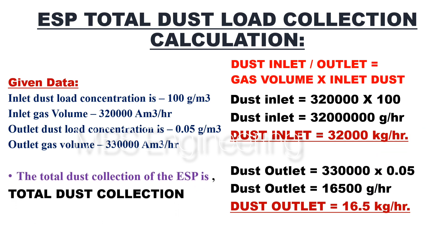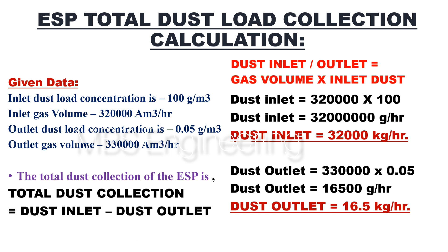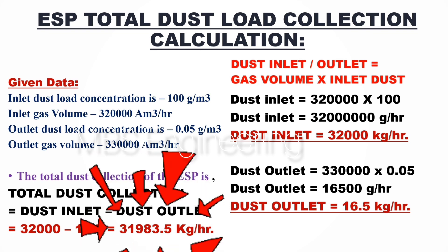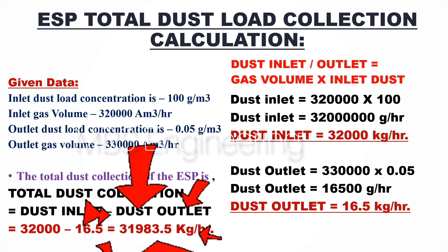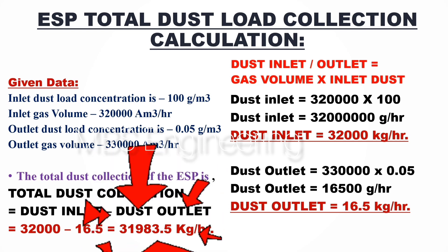Finally, total dust collection is equal to the dust concentration at inlet minus dust concentration at outlet — that is, 32,000 minus 16.5. As per the given parameters and calculation, the obtained value of ESP total dust load collected is 31,983.5 kilograms per hour.